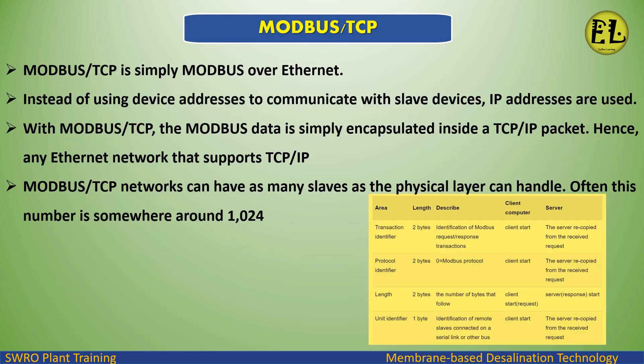Modbus/TCP is simply Modbus over Ethernet. Instead of using device addresses to communicate with slave devices, IP addresses are used. The Modbus data is encapsulated inside a TCP/IP packet. Any Ethernet network that supports TCP/IP can use Modbus/TCP, and these networks can have as many slaves as the physical layer can handle — often around 1,024.